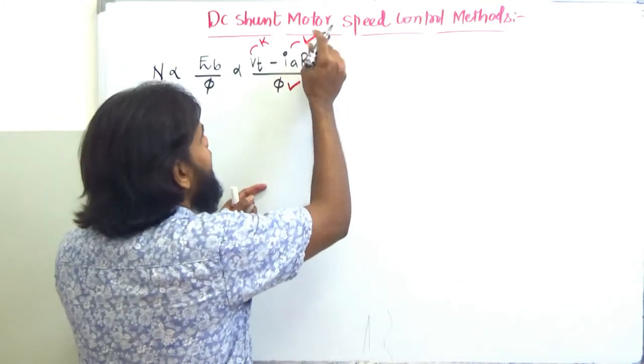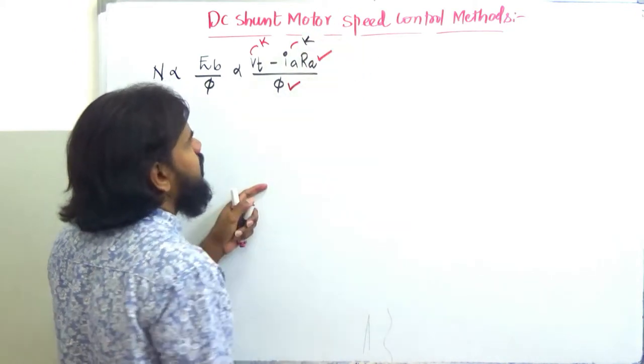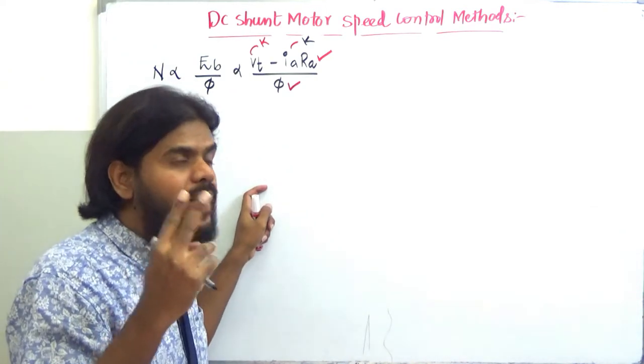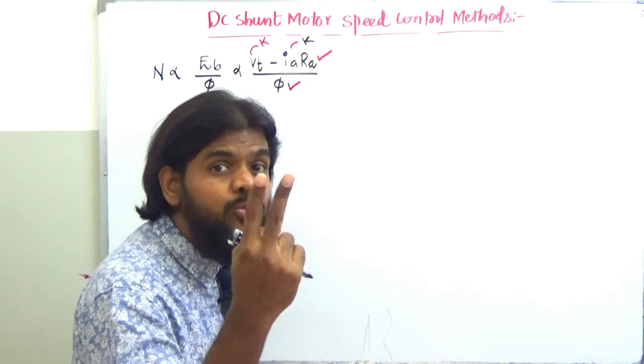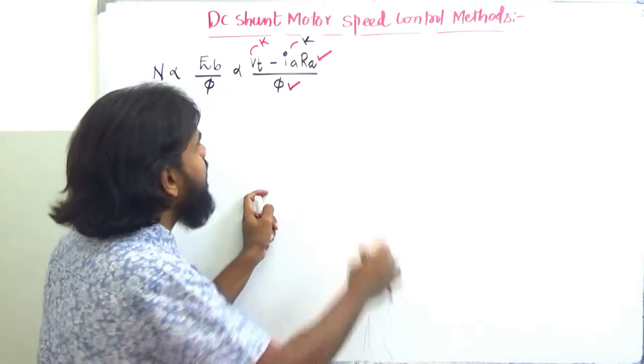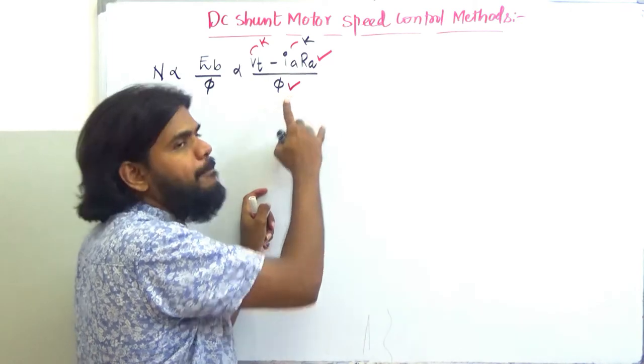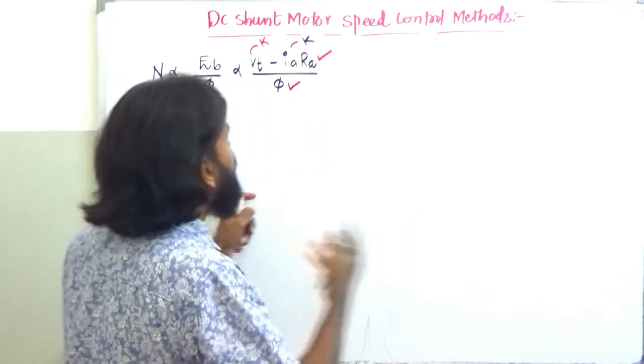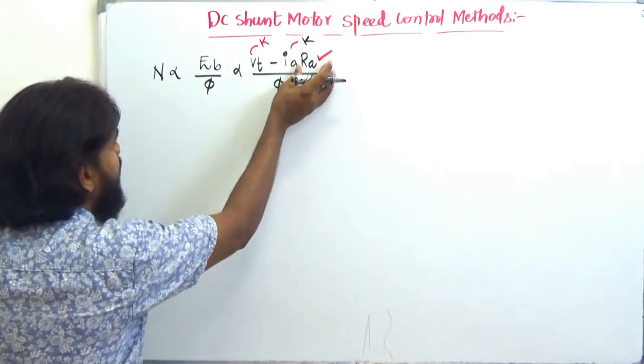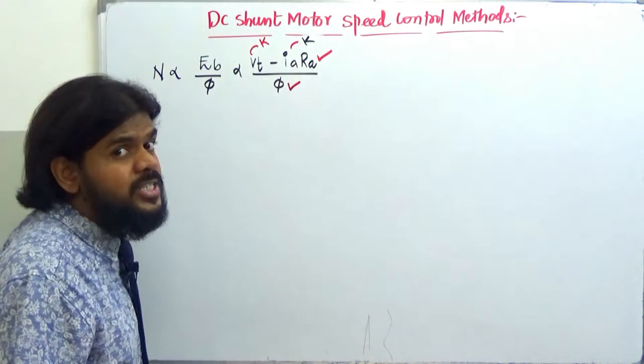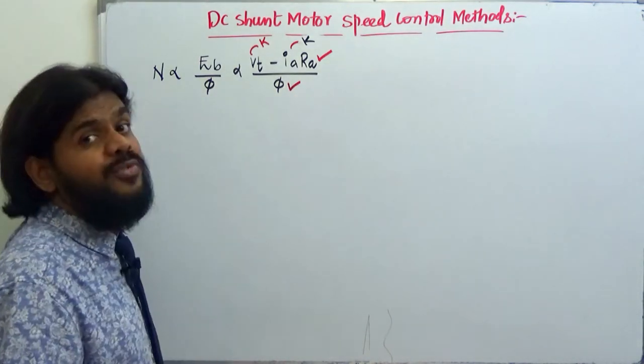With constant load, Ia is unchanged. So I have the scope of controlling speed by only two ways: one is by controlling Ra, and the second is by controlling flux φ. This gives us two distinct speed control methods.